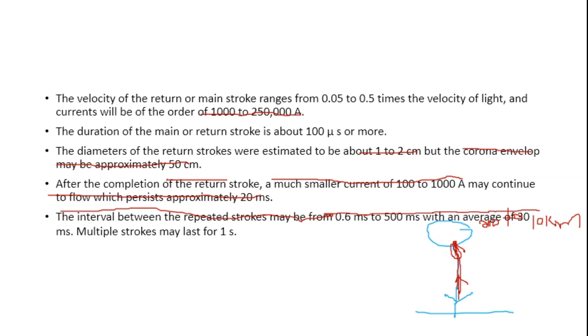The interval between repeated strokes varies from 0.6 milliseconds to 500 milliseconds, with an average of around 30 milliseconds. Multiple strokes may be present for up to one second, meaning total lightning duration may extend to one second. The peak return current from ground is around 250,000 amperes, with a rate of rise varying from 10 kilo-amperes per microsecond or 10^10 amperes per second. The time interval between successive strokes, number of strokes, duration, discharge current, rate of rise, wave front, wave tail, and probability distribution are all key parameters.